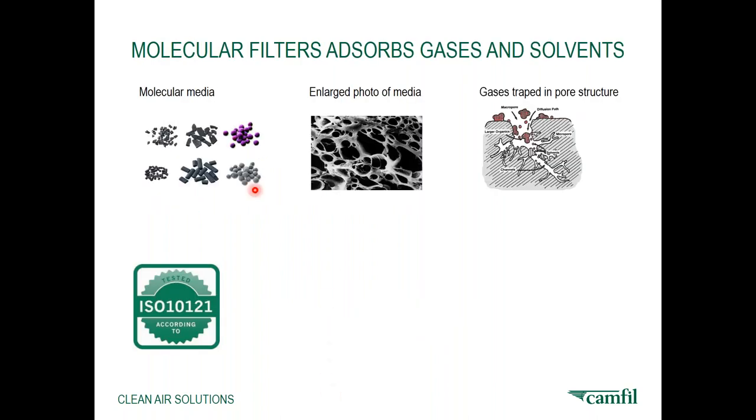We have mentioned molecular filter several times in this presentation, and this type of filter is used to remove odor, smell, or hazardous gases. Instead of mechanically filtering particles, molecular media adsorbs gases and solvents. A variety of molecular media exist depending on the target gas to trap, as you can see in the picture to the left. Just 1 gram of molecular media has up to 3,000 square meters of surface in the micropore structure, as in the picture in the middle. In the final picture, we see how molecules are trapped in the micropore structure. Remember to always ask for the molecular test standard when considering molecular filtration.